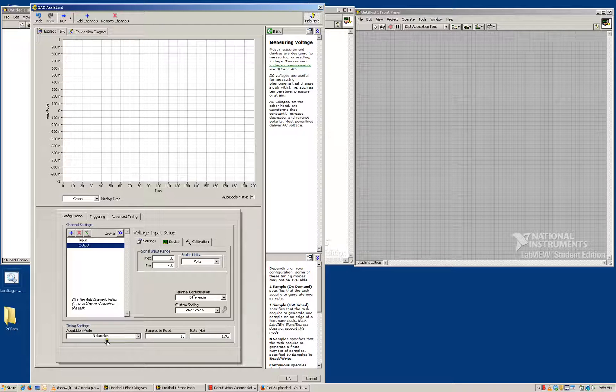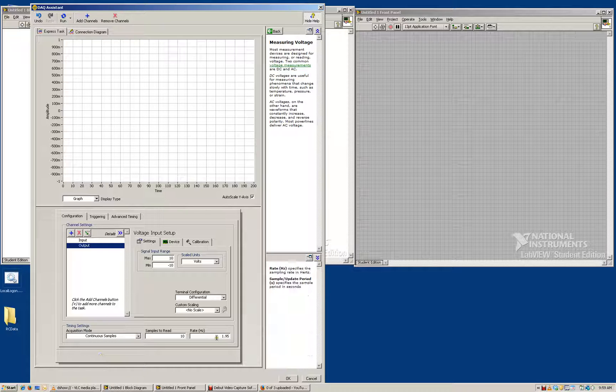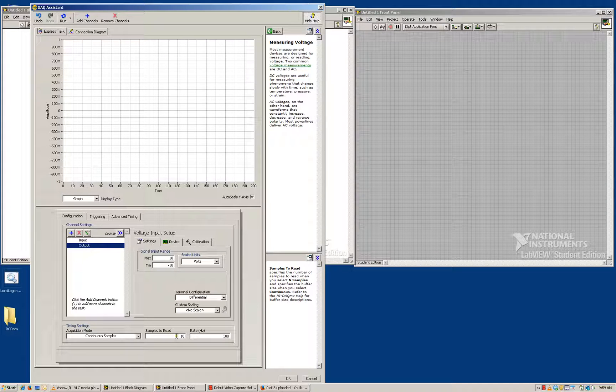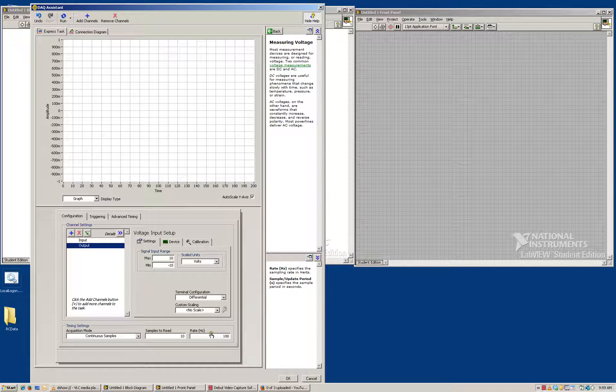The other thing I need to do is set my acquisition mode. I'm going to configure this to do continuous samples, because we always want to be making data measurements. I'm going to set this at the maximum rate — for this card in particular, I'm using a data acquisition card, the 9219, which has a maximum sampling rate of 100 Hz. Then I'm going to set the samples to read — this is how often it's going to update my screen — I'm going to set my samples to read to about 10. So every tenth of a second, it's going to take measurements at 100 samples per second, and every 10 data points it's going to update the screen and update the data file.